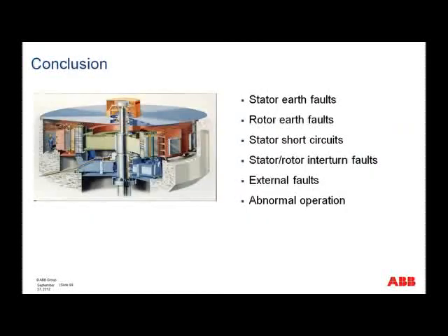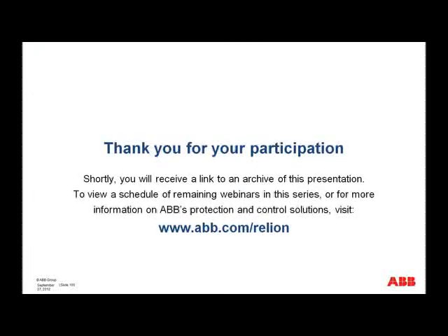So okay, to conclude then, this is the same slide that we saw many slides ago. I said we would look at all the different types of protections: the stator-to-earth faults, rotor-earth faults, stator short circuits, stator-to-rotor, interturn fault, external faults, and all the abnormal operating conditions. And we would go through them, and we would see what protection we had in our generator protection package to handle these. So, okay, thank you very much. Now I've come to the end of the presentation.